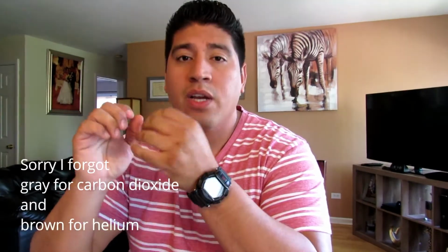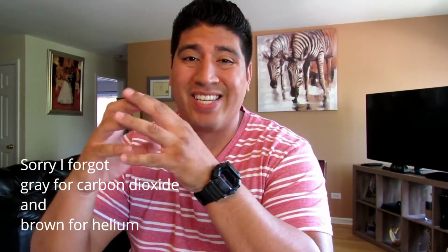So please remember the scavenging system. Another thing, guys, that you have to learn is the color code system for the cylinders. For example, oxygen is green, nitrous oxide is blue, nitrogen is black, and yellow is for compressed air.